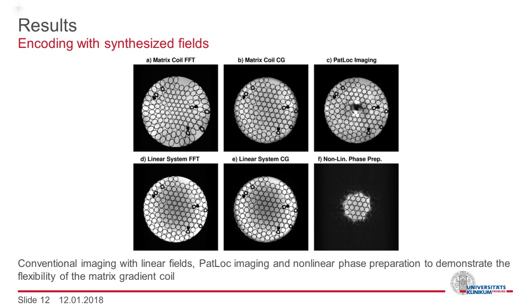The synthesized spatial encoding magnetic fields have been used for initial imaging experiments. The first image was encoded with synthesized linear encoding fields generated by the matrix coil. Expected distortions from field nonlinearities occur in this image, which can be corrected for by using a conjugate gradient reconstruction. For reference, images acquired with the built-in gradient system are depicted, showing a straightforward Fourier transform and a conjugate gradient reconstruction for comparison. To demonstrate the flexibility of the matrix coil, PatLoc imaging with quadratic fields and nonlinear phase preparation are also shown.